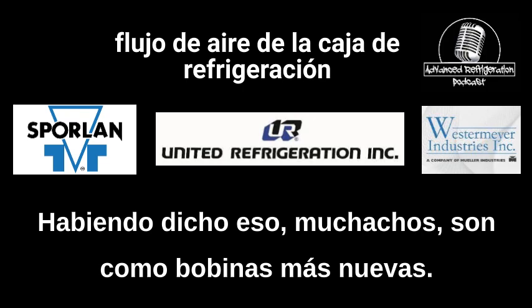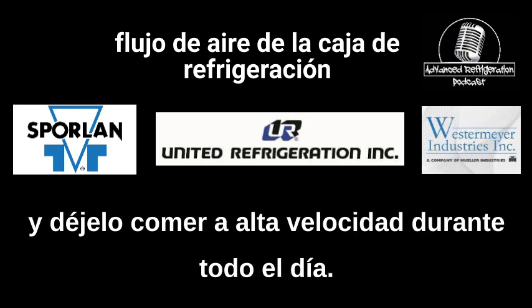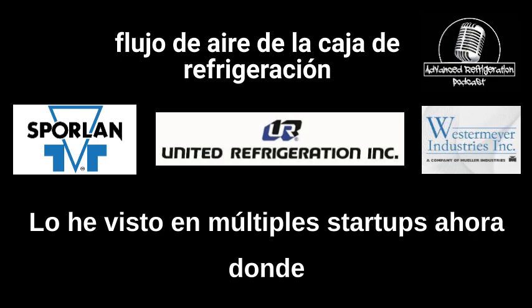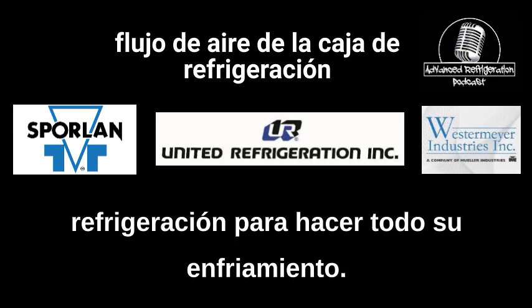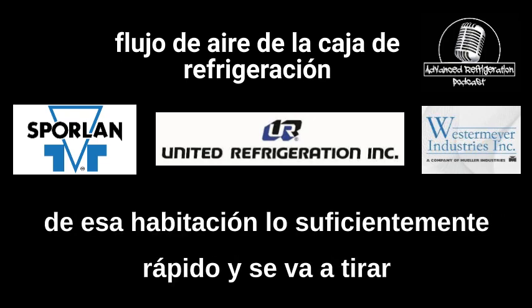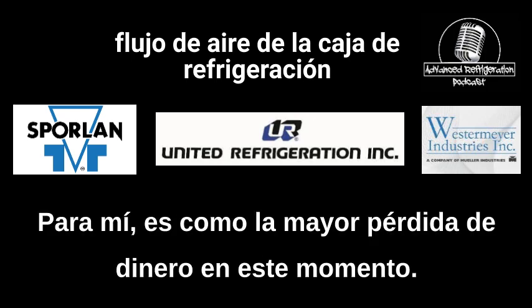With that being said, guys, with newer coils, if you do not have anything to control the fan speed and the customer's not doing it, make sure you jump that thing out and let it run high speed all day long. I've seen that on multiple startups now where boxes struggle to make temp after defrost, and I've seen the fan speed not disabled, so it was running low speed. That low speed's not enough in refrigeration to do all your cooling. It's not going to remove enough heat out of that room fast enough, and it's going to throw off the TD on the coils. So make sure you're in high speed. I've only seen one customer utilize the fan speed control. To me, it's the biggest waste of money right now.